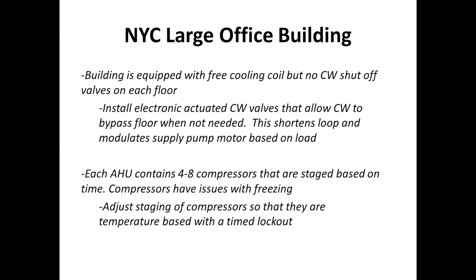We could actually install electronic actuated condenser water valves. Essentially what this did was, when that building was working in economizer mode, if there were floors that didn't need that condenser water, we could bypass the floor, which reduced the pressure on the supply pump for this building. It could actually ramp down the supply pump VFD.